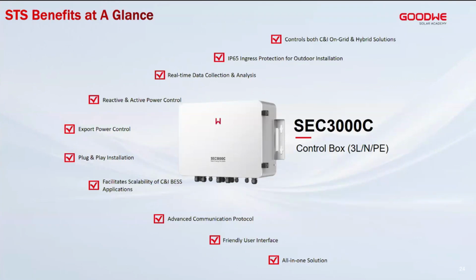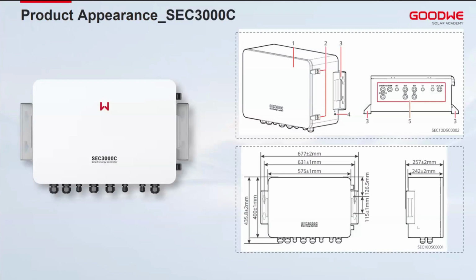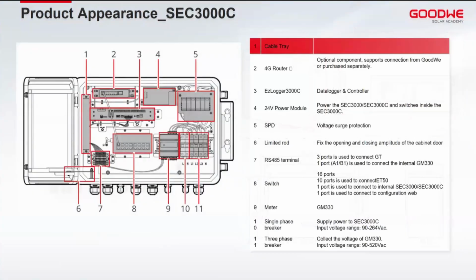So yeah, you can use your computer, web-based, to connect and set up your system. And similarly, it's an all-in-one solution because in the control box, you'll have the data logger, EzLogger3000C. You'll have your smart meter as well, the GM330, to monitor the grid and also control the products that are installed locally. So how does it look like? These are the sizings, very compact, and a number of already prefabricated points or holes at the bottom for the cable connections. So yeah, easy to mount, easy to secure. It also has plugs or locks at the sides, key locks, so you can lock them with your key just for safety.